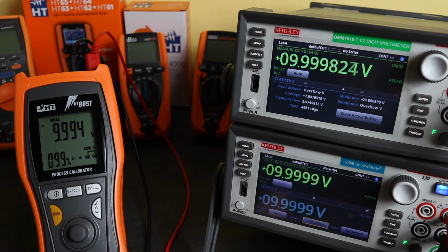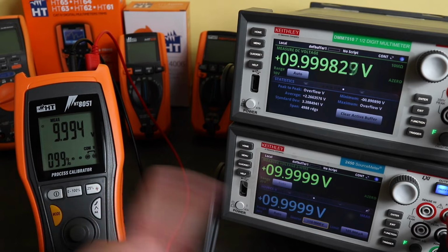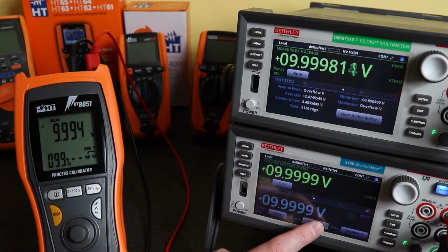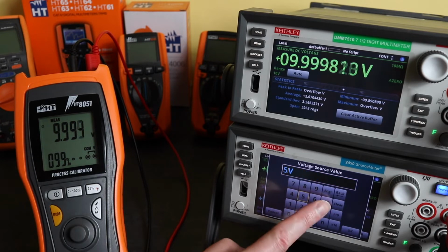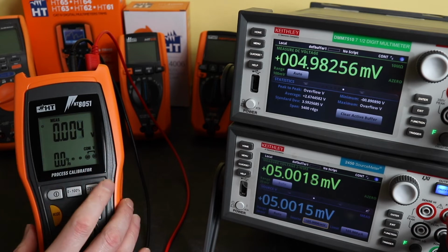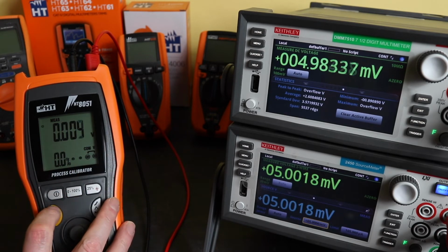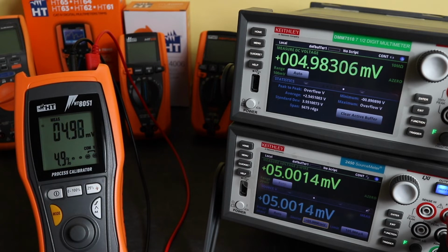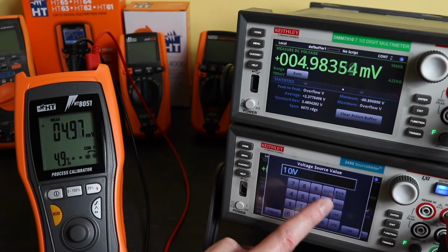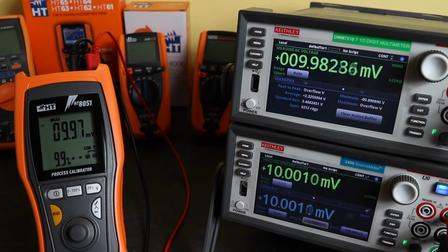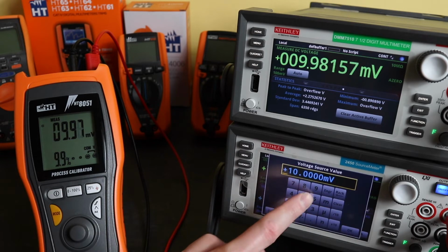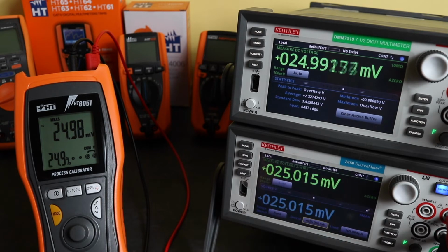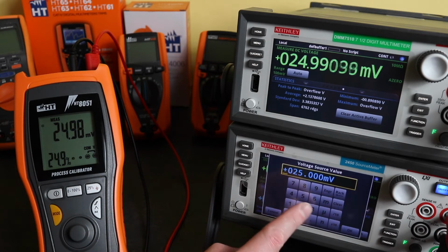9.994 next 9.999. Okay, so next range on this is the 0 to 100 millivolt measurement. So let's go down to 5 millivolts, I think. And you can see right at the bottom scale on the voltage on there, but if I hit the mode button, we're into millivolts. And we can get 4.97 against 4.98 on the DMM7510. Let's go 10 millivolts. 9.97, it's 9.98. Oops, 25 millivolts. 24.98, 24.99. So pretty respectable, really.